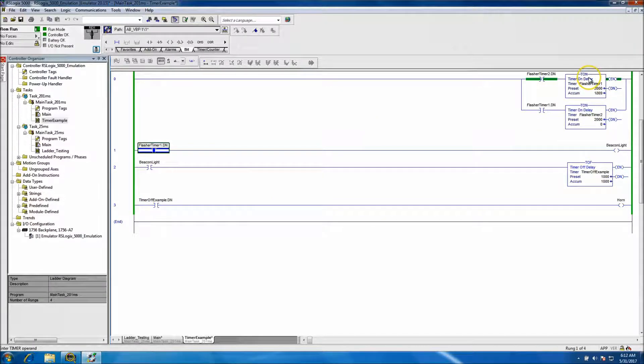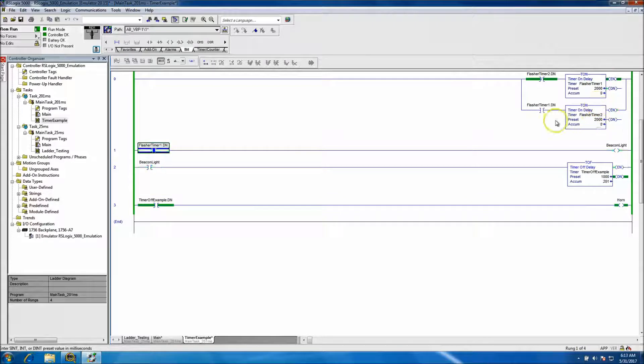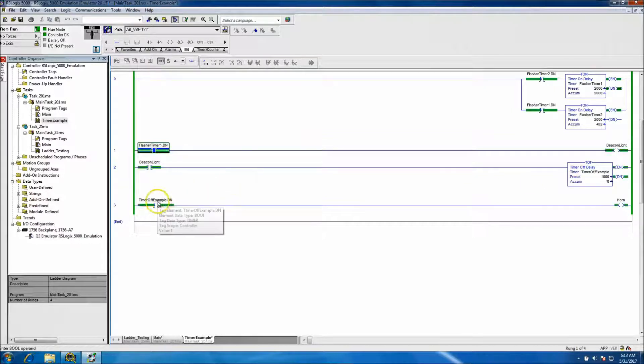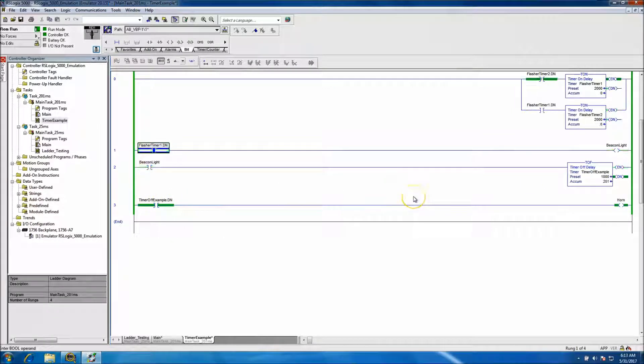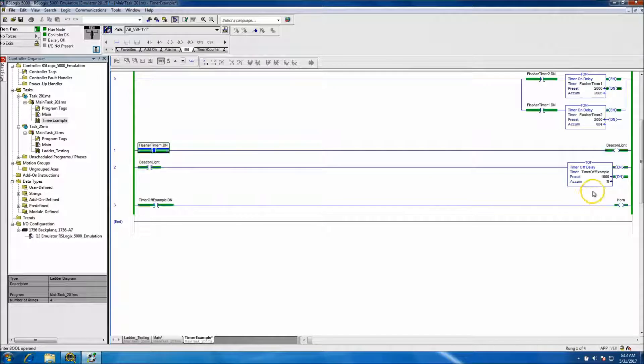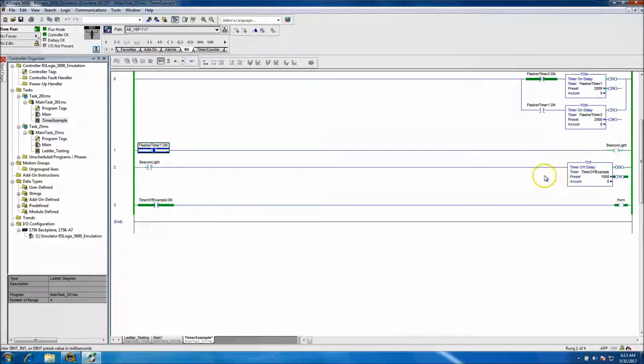To review: a TON timer done bit does not come on until the timer has completed the preset value. Then it comes on and makes the done bit. On the counter side of that, if you have a TOF, basically the reverse statement happens. As soon as it's made, it holds the done bit until the timer preset is done, and then it drops the done bit.